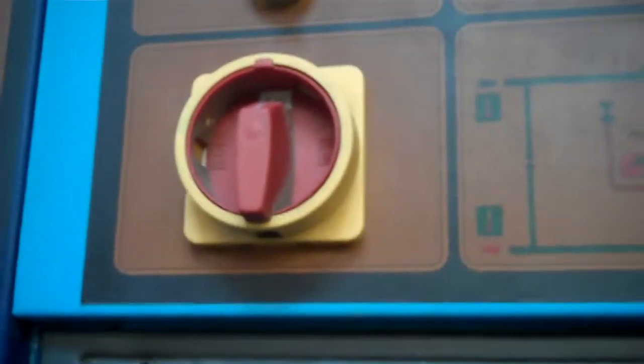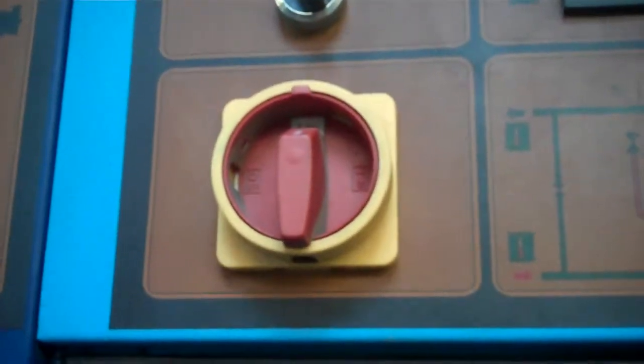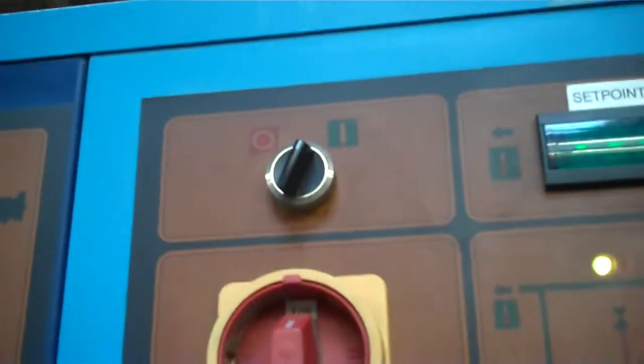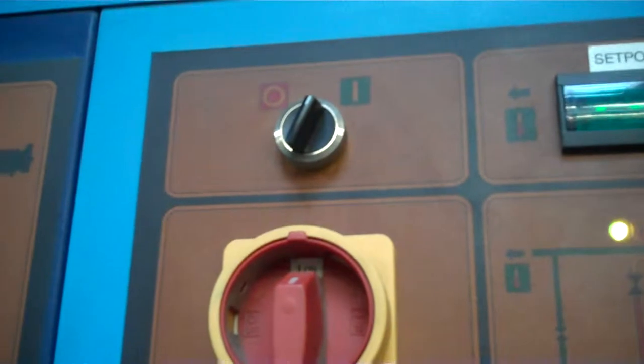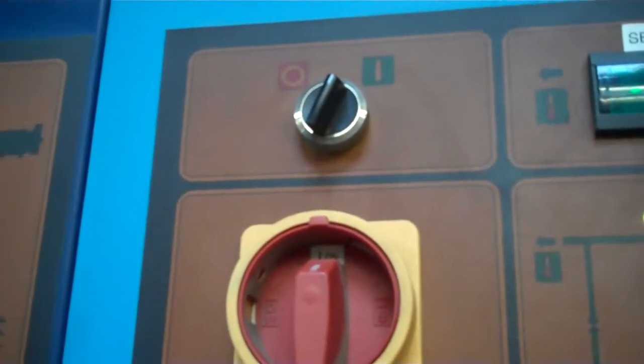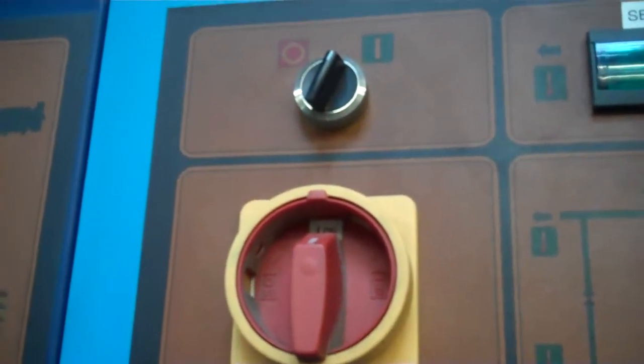What we have here is we're going to go ahead and just turn our power on right now. And the first thing you do is you turn that main power disconnect button on. And then you turn the secondary power button on. Then after a few seconds, the various temperature controllers will show you the fluid reading. Right now we're still heating up the fluid at the inlet and outlet connections on the back of the unit. We got it up to about 67 Fahrenheit right now. We're probably going to heat it up to about 75 before we actually turn the chiller on.